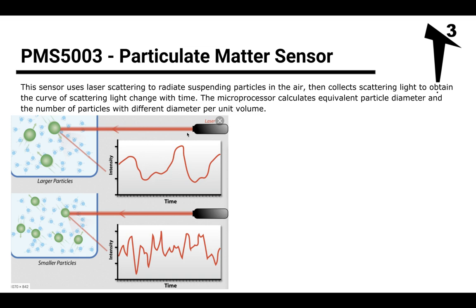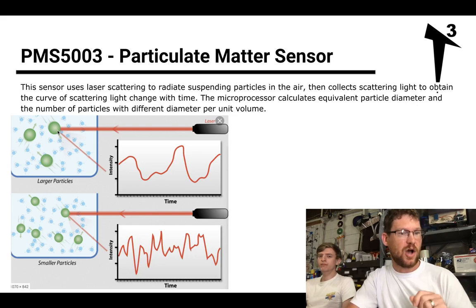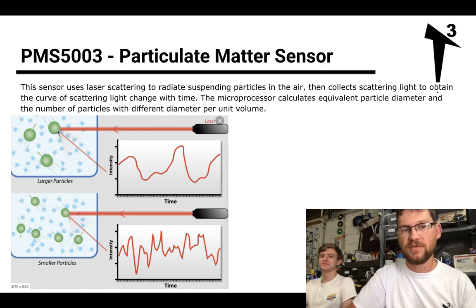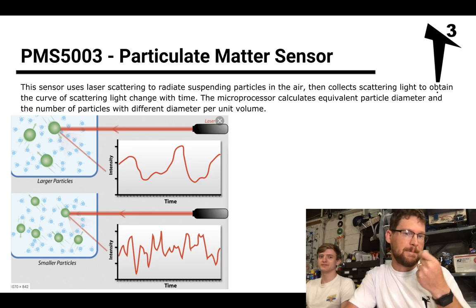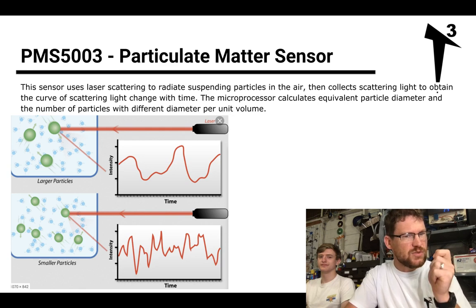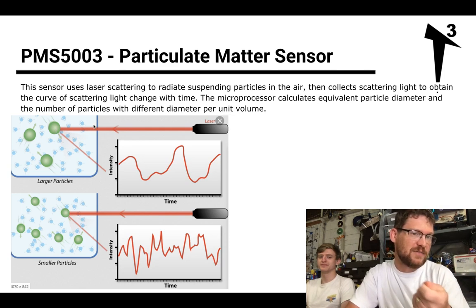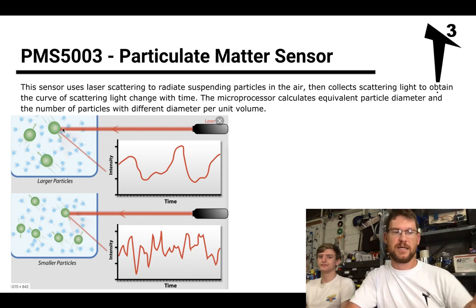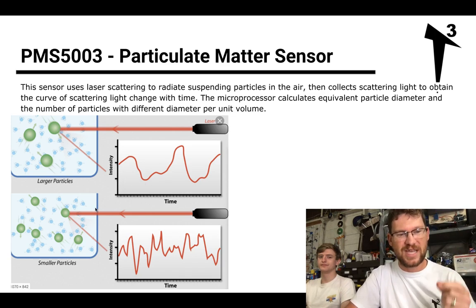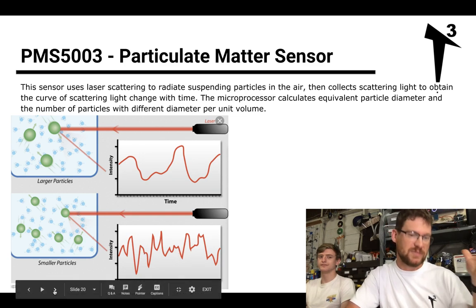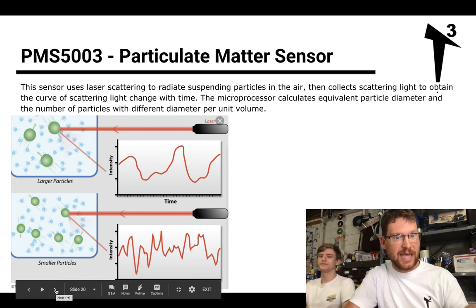How does the particulate matter sensor work? It uses a little laser inside to bounce light off of particulate things moving around in the air. Particulates can be everything from dust to smoke to pollen — anything that's really tiny. If the laser encounters something big, it creates one kind of signal; for tinier things, it creates another kind. The data is correlated scientifically, and you can get the amount of certain sizes of particulates in the air.